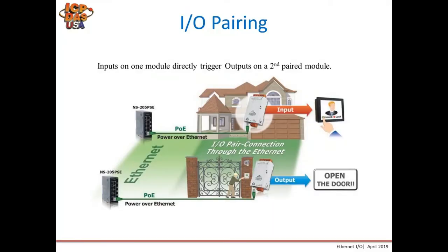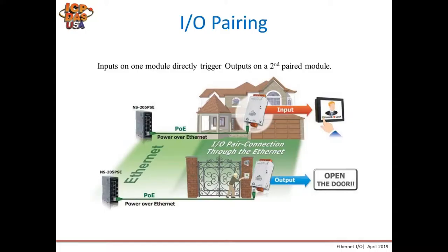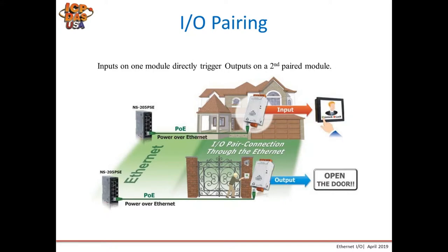This slide shows our IO pairing feature, which is exclusive to the ET-7200 and ET-7000 series. In pairing mode, an input module on one end and an output module on the other end are paired so that when an input on one module turns on, the corresponding output on the other module turns on. A practical example is a house and gate scenario: when someone pushes a button at the gate, it signals an input within the house, allowing someone to remotely unlock the gate over Ethernet without being at the terminal.